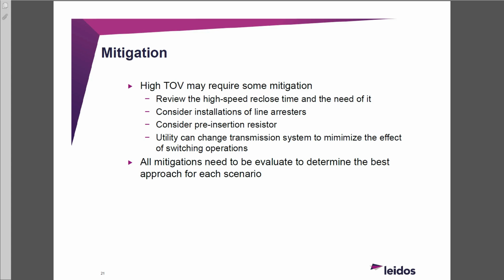What you're really talking about is tower maintenance, where you use portable arc gap devices out in the field. I don't think it's so much an issue in a substation, you've got arresters and everything for that. I agree, but I can tell you the way some of our folks have interpreted that, they would want it within the station too. Well, get a PE to sign off otherwise.